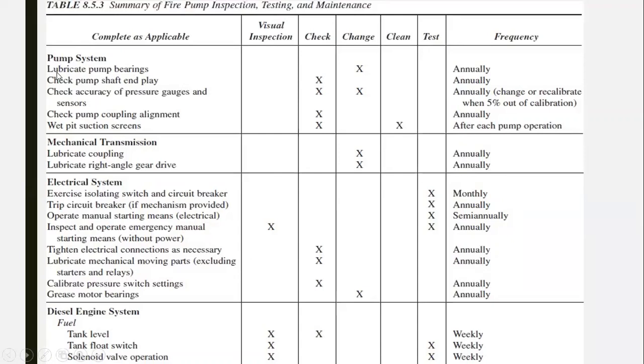For the pump system, lubricating the pump bearings is done annually. Checking the pump shaft end play is also annual, etc. So it gives you the whole list of tests, inspections, and changes you would like to make, with all the recommendations proposed by NFPA in case of absence of manufacturer recommendation. Otherwise, you have to follow the manufacturer recommendation. This one talks first about the pump system, mechanical transmission, electrical transmission, and the diesel engine system.